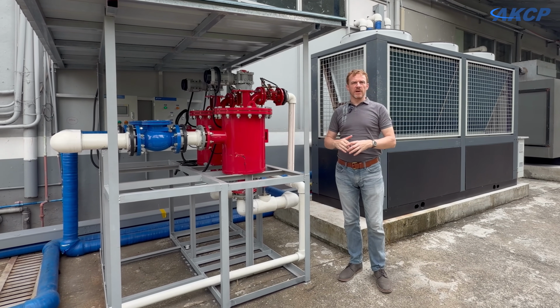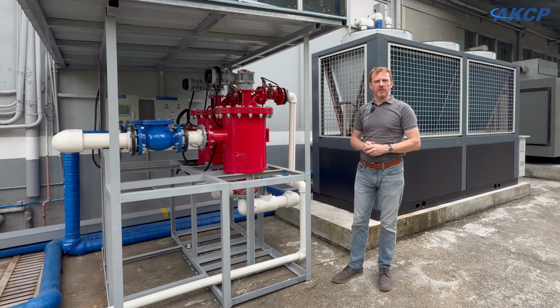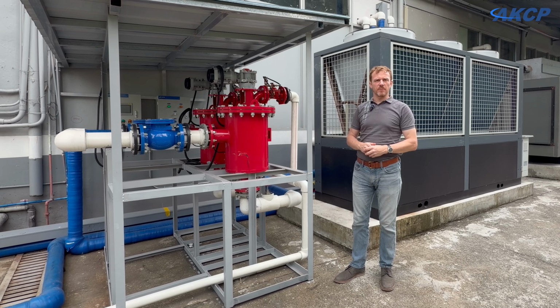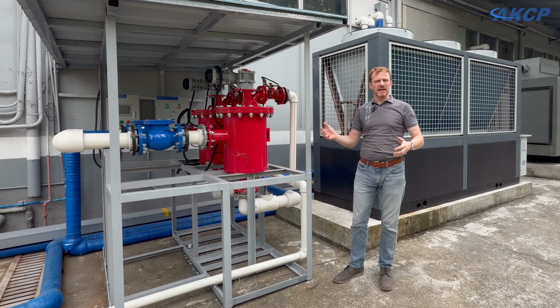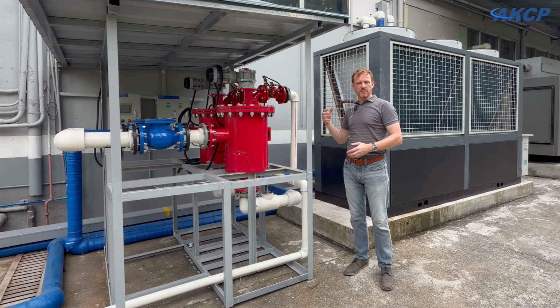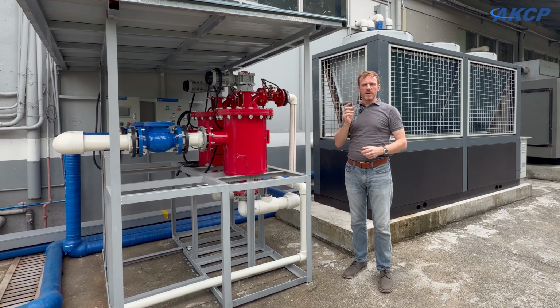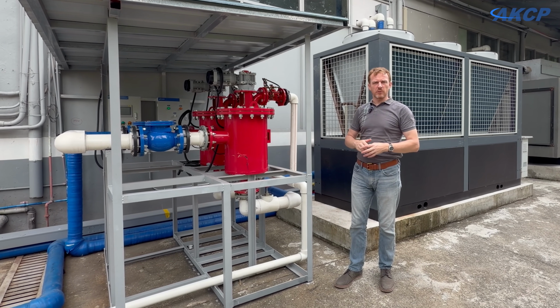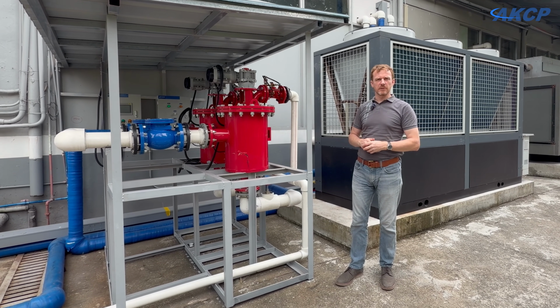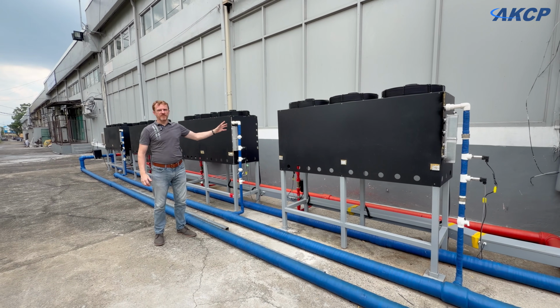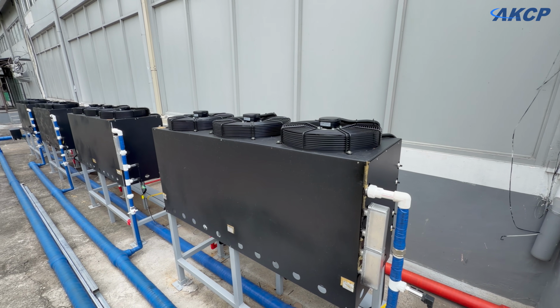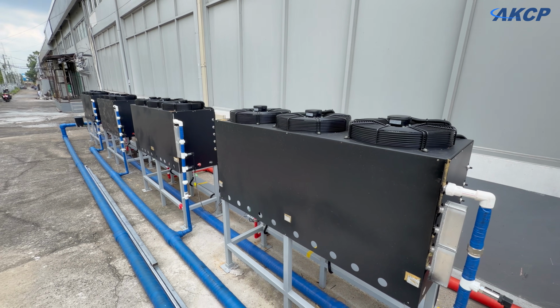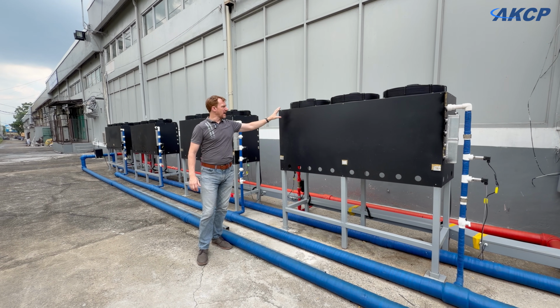If it is cool enough outside, or if we are operating with GPUs, for example, where we can have much higher return water temperatures than perhaps the chiller can take, we can also send the water to what we call our pre-free. Let's go and take a look at those. So here we have our pre-free units. These are basically dry coolers. We're sending the water from the data center back to here.